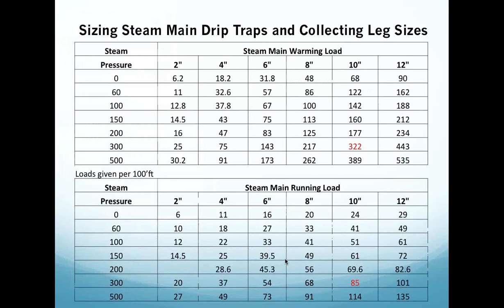I want to go into sizing a couple different applications so you can see what we're going to be looking at. And a couple of the applications that I've chosen, one of them is steam main drip trap sizing. And what I wanted you to see is something that I believe is important from a safety as well as a capacity and a performance standpoint. In this particular chart, we're looking at sizing steam main drip traps and collecting legs based on a warming load and a running load.